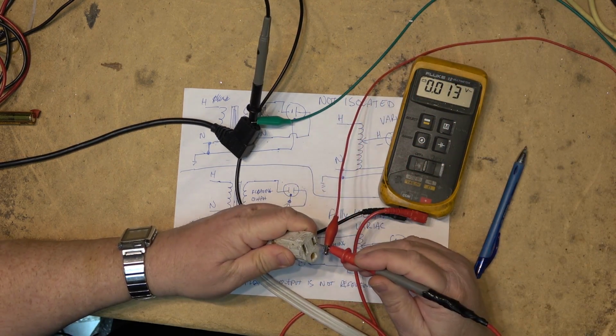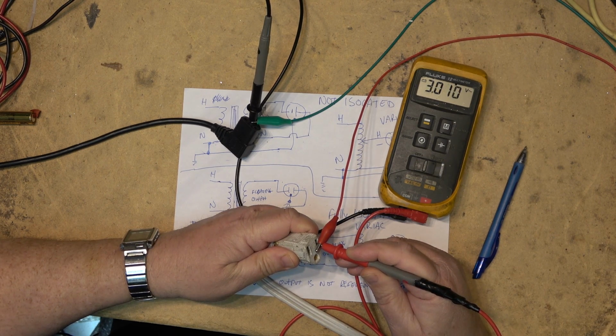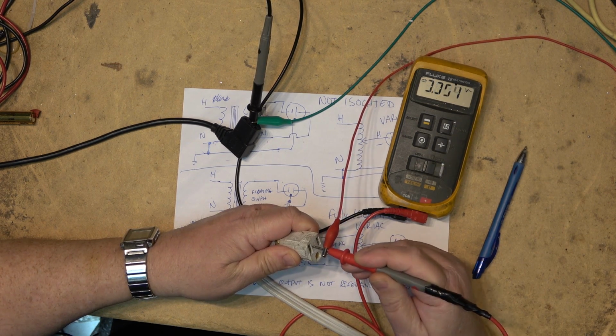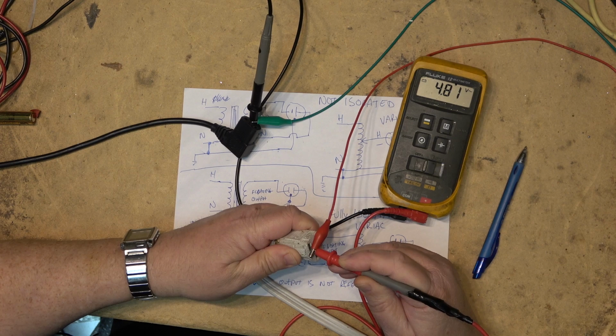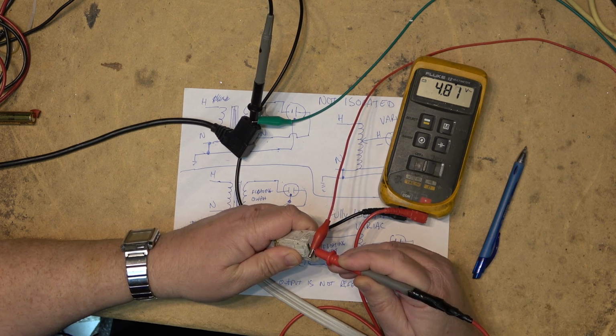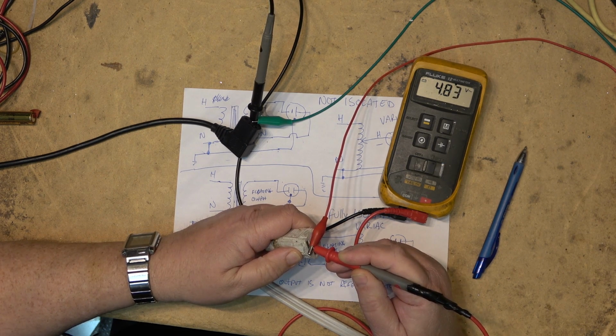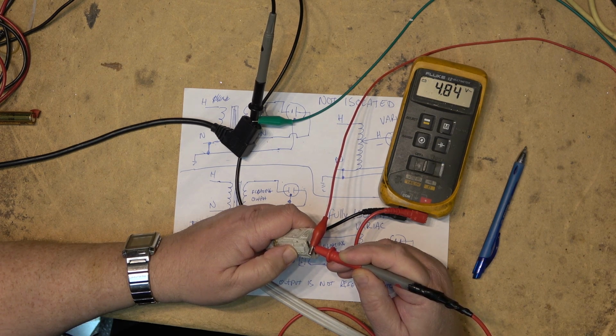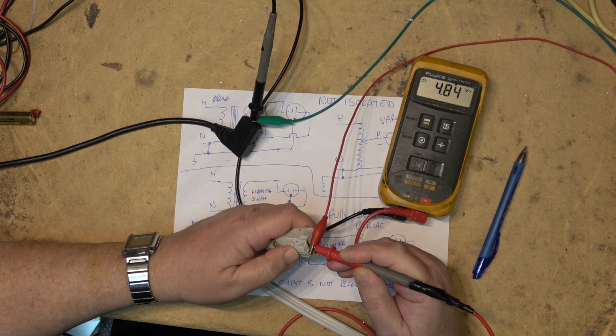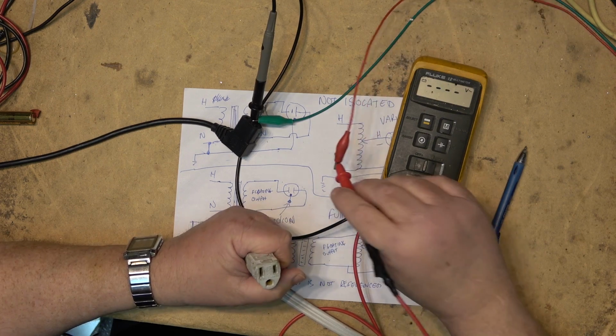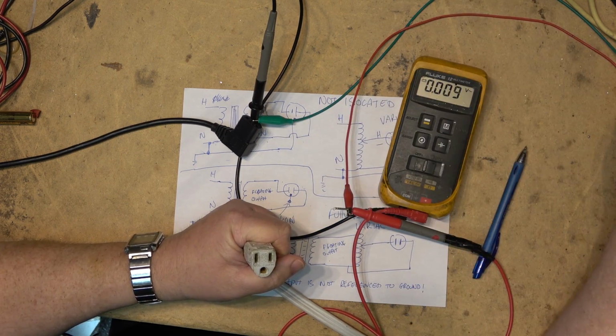So this will dissipate the induction. And now if I go to my isolation transformer, you'll see that I got like 3 volts. And on the other side, I've got like 4 volts. And that's just because the 330K resistor is allowing a bit of a rise there, just still from induction if I went to a smaller value. But the thing is, I could put a jumper wire in here.